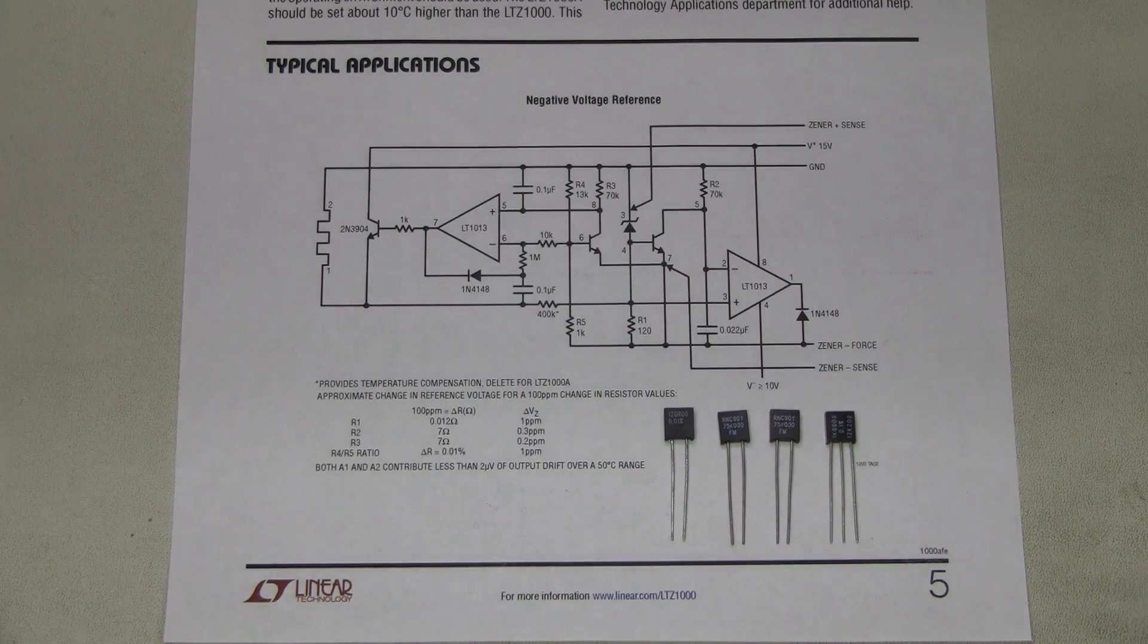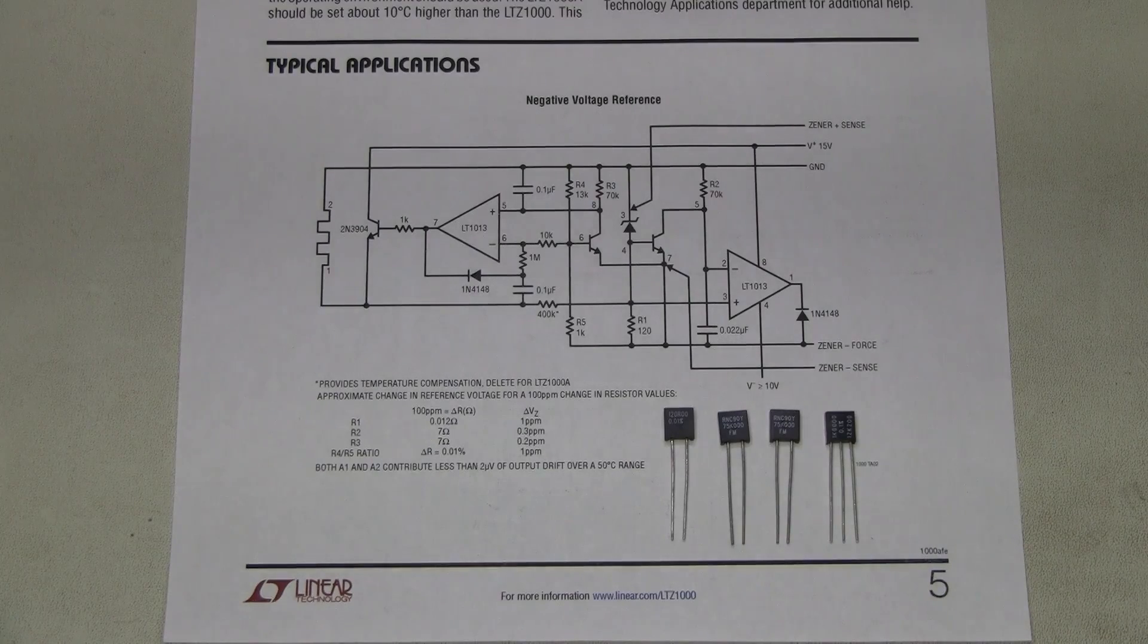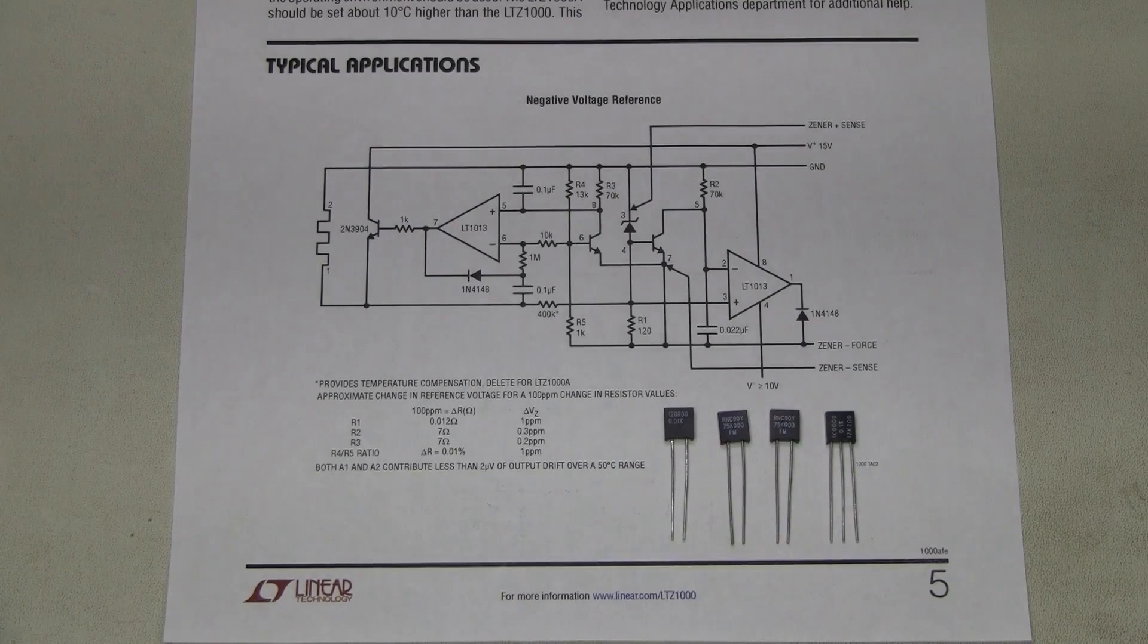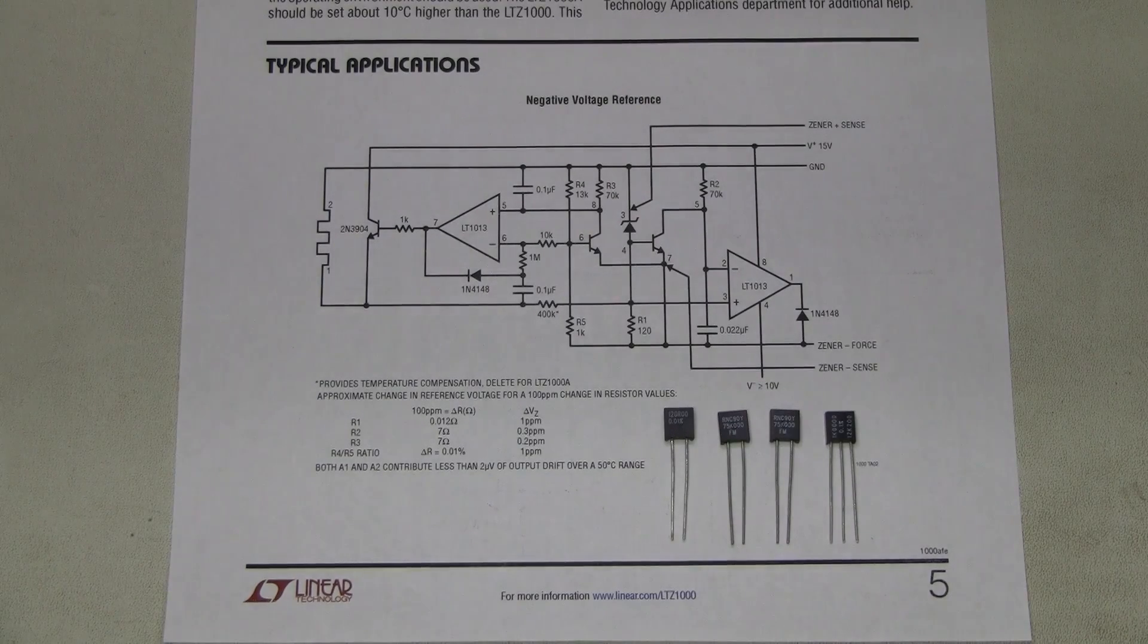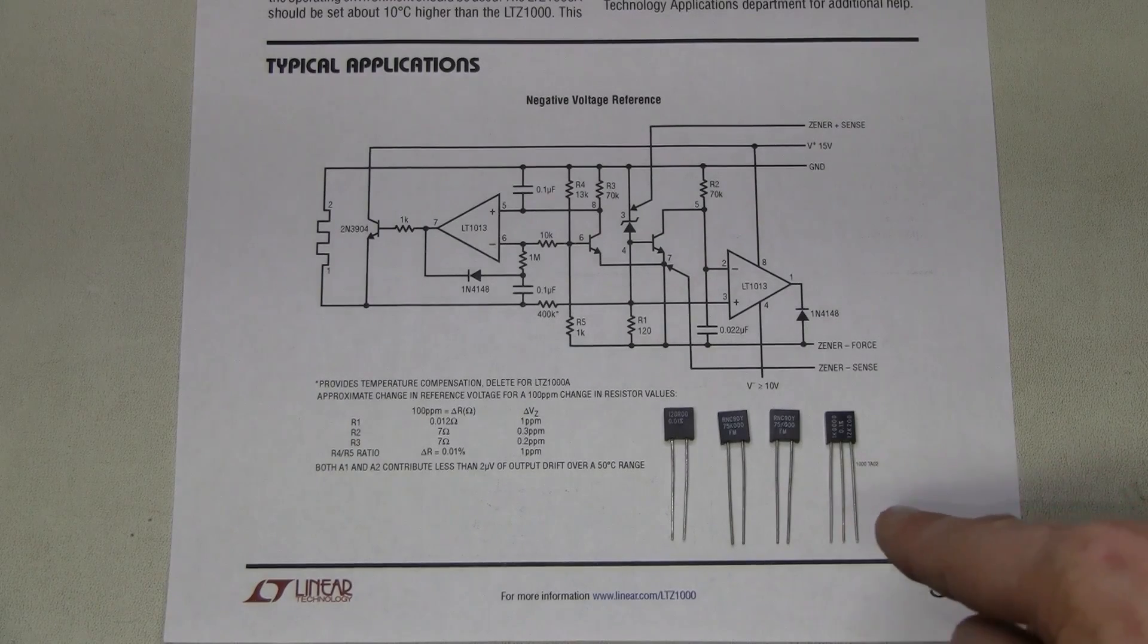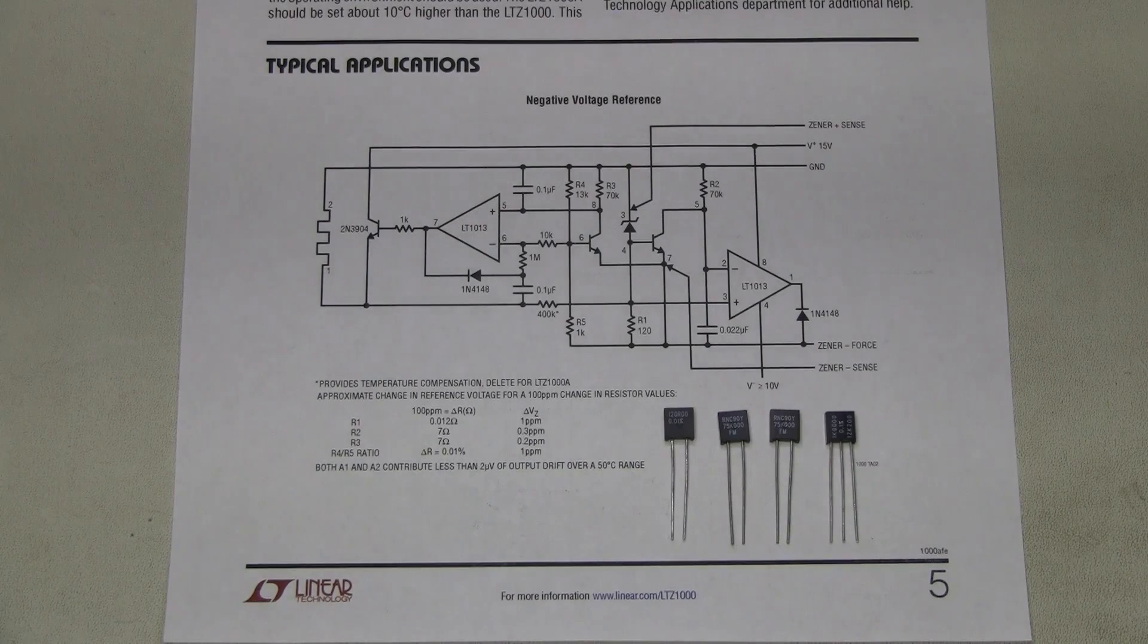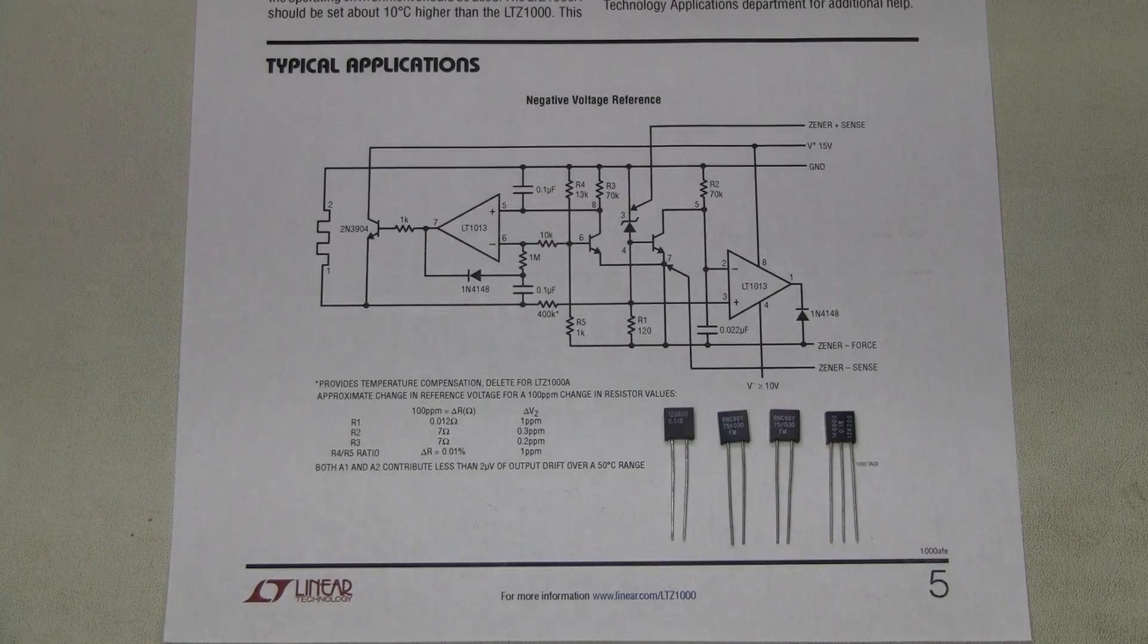The resistors should be stable to, let's say, a few ppm a year and under 2 ppm per degree C temperature drift. The resistors in one package should track each other within 1.5 ppm per degree C and also something like a few ppm a year aging.